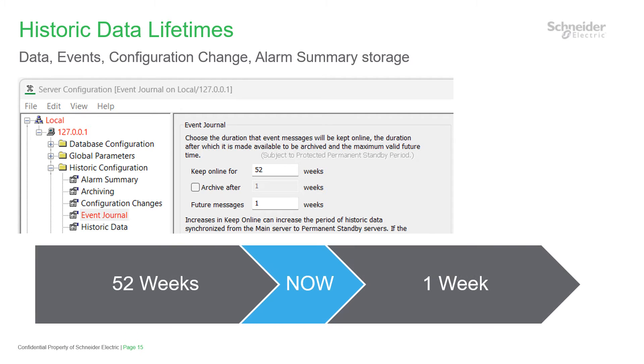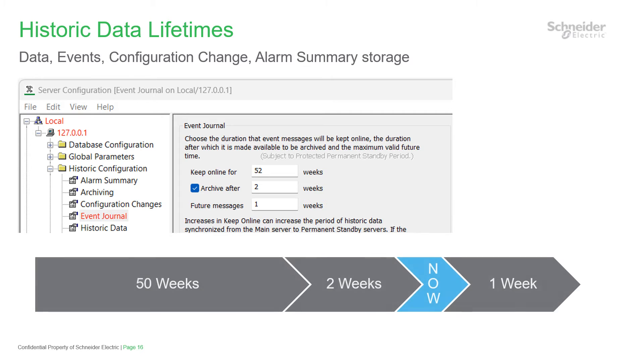Starting with lifetime, and with historic point and accumulator data, let's take a look. Here are the basic settings and you can see that the online period is the first setting. Data is stored for at least this period and then deleted at midnight UTC, Sunday to Monday. The future setting is used to filter out data received from devices which might have an invalid clock setting. Archiving is an optional feature used less these days because disk storage is plentiful, and the archive process also exerts extra historian load particularly on busy systems. If you don't need it please don't use it. If you do require archive, check out the F1 help to see how to set it up. Remember that the archive index is kept online and that older data from seldom connected devices will not be archived if it's received after the archive time.